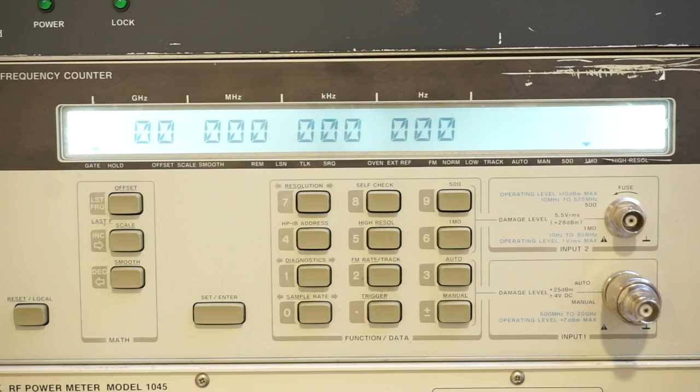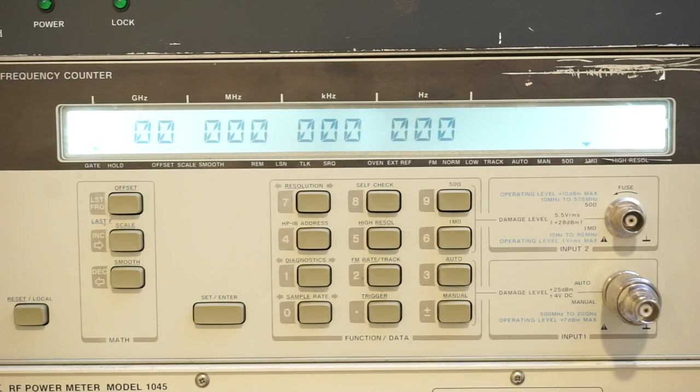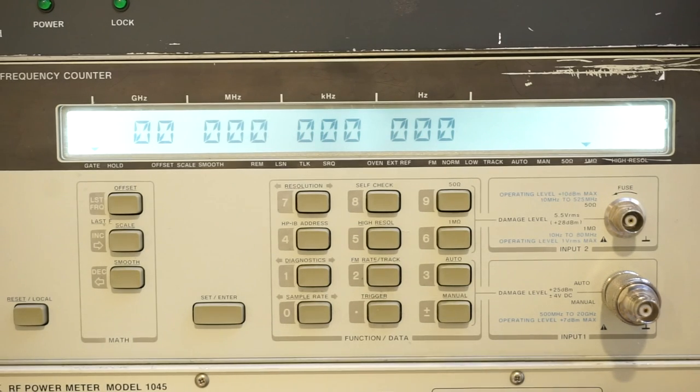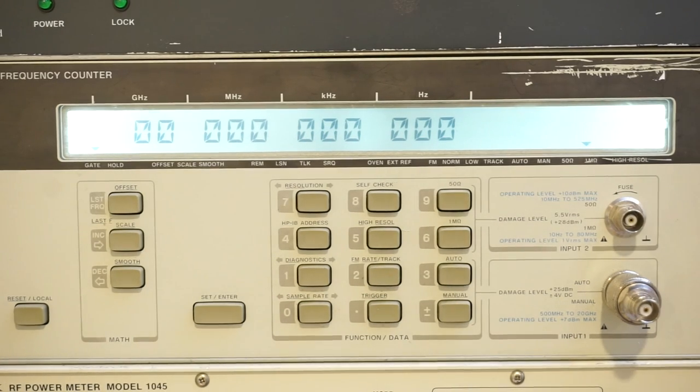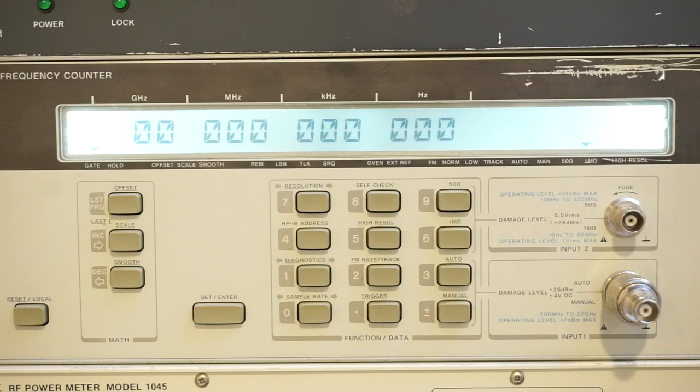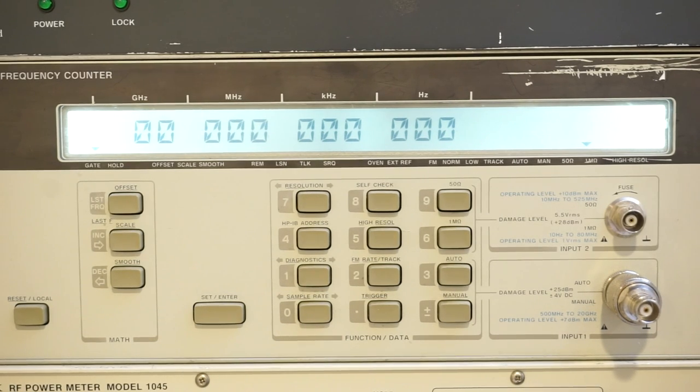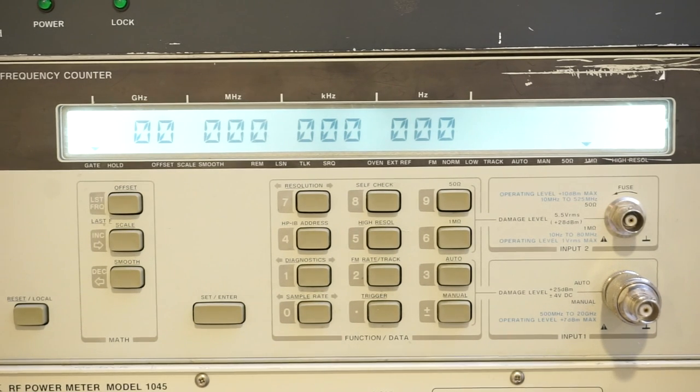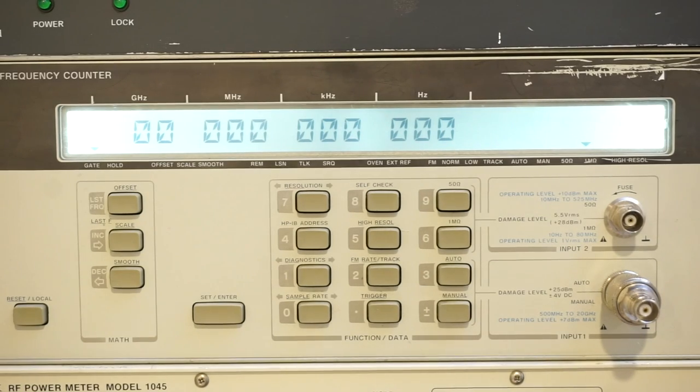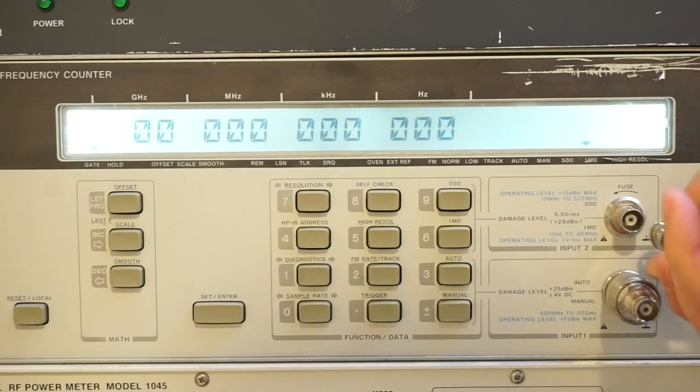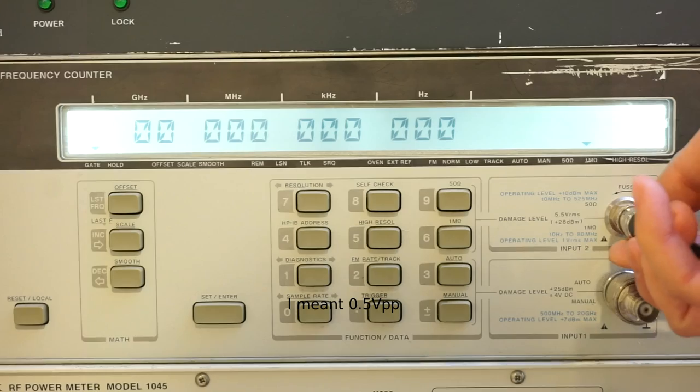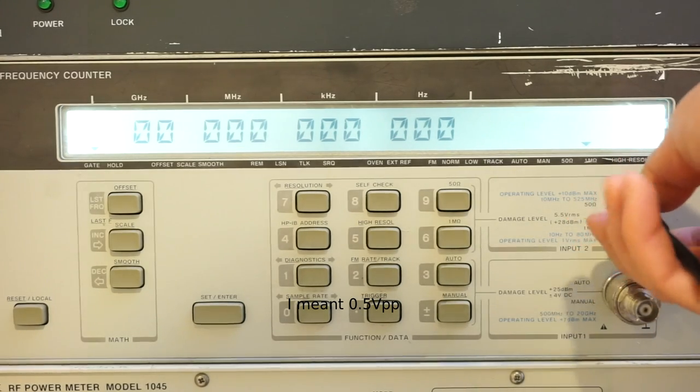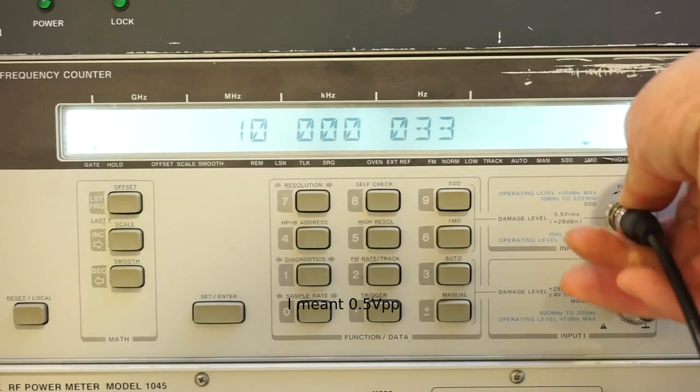And if you recall, I already calibrated it with this rubidium frequency standard sitting on the top. And now I turned on the Wavetek 395 and had it output a 10 MHz square wave at about 0.5 volt peak-to-peak level.